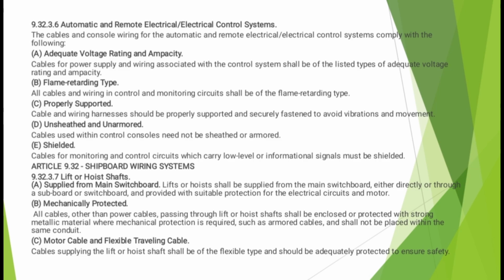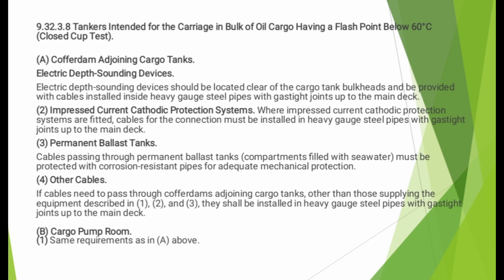Cable supplying the lift or hoist shaft shall be of the flexible type and should be adequately protected to ensure safety. Tankers intended for the carriage in bulk of oil cargo having a flash point below 60 degrees Celsius. Closed cup test. Cofferdam adjoining cargo tanks. Electric depth sounding devices. Electric depth sounding devices should be located clear of the cargo tank bulkheads and be provided with cables installed inside heavy gauge steel pipes with gas-tight joints up to the main deck.